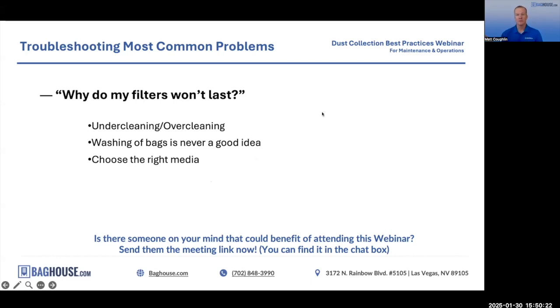If you're in a pinch, you've got to do what you've got to do, right? Sometimes if you don't have an extra set of filters, which we of course recommend you do, and your system's down, some people will go and launder them just to get their system up and running. I get it, but you should not expect those filters to last too long. That should be a stopgap and not something you do as a regular process.